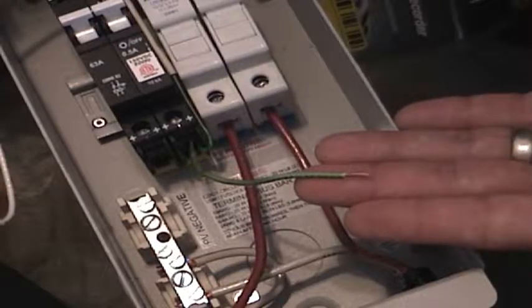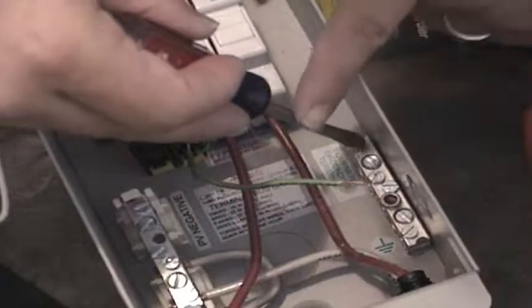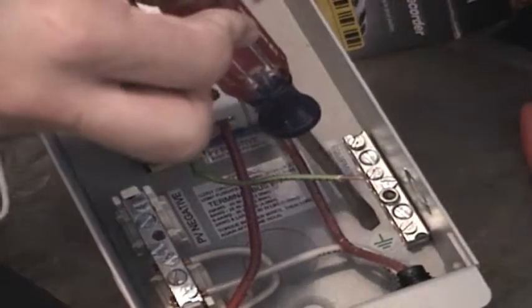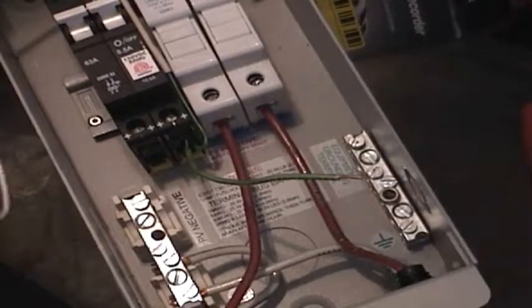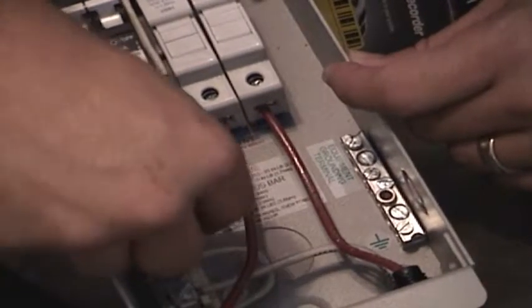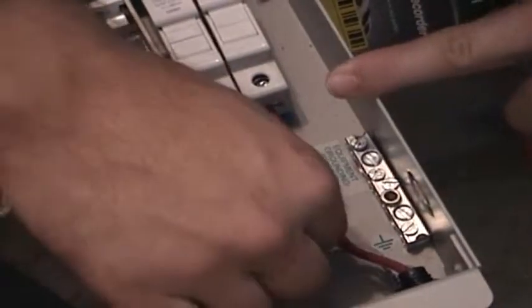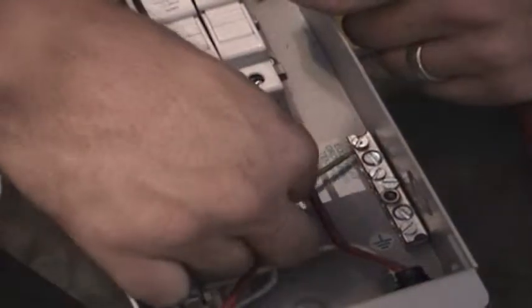Now that we have about 1/2 inch of the skin removed from the green ground wire, let's go ahead and loosen the top screw on the ground bus. The ground bus has a sticker with the little ground symbol next to it. Then let's maneuver our green wire into place. You may have to go underneath some of the other wiring. Go ahead and feed the wire into the hole. There we go. Make sure that the wire is inside the hole completely without any of the exposed end hanging out, and then let's re-tighten the screw. Make sure it's plenty tight.